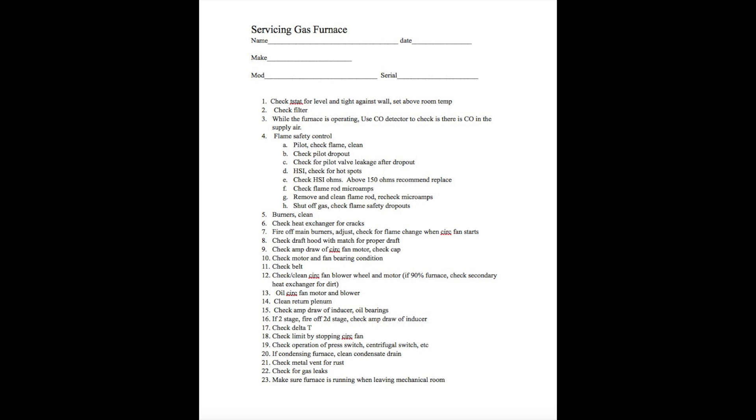Check flame rod microamps. You're going to have to go to the flame rod in this thing. Find the flame rod, put your microamp meter in series with it, and check to see what the microamps are reading when the thing's running. These flame rods generally are on pilotless ignitions. They're sticking into the flame, usually opposite side of where the hot surface igniter is. You're going to check the microamps on that before you do anything else. Then you're going to go ahead and remove and clean the flame rod. You can clean it with steel wool, you can clean it with sandpaper. It does need to be clean. Then recheck the microamps and see if you made a difference.